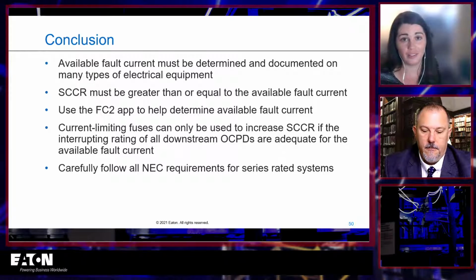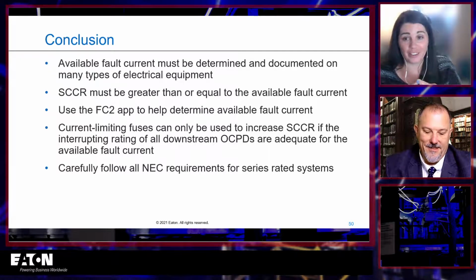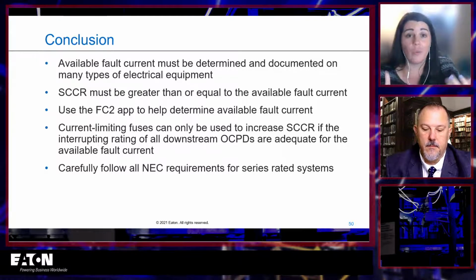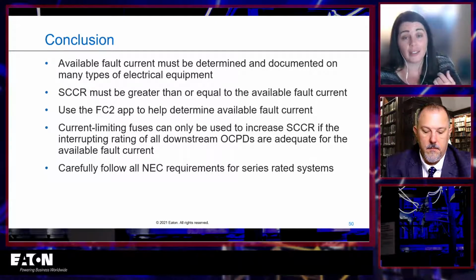So in conclusion, available fault current. We got to know what it is, right? We have to determine what it is. We have to document it. We have to actually field mark a lot of pieces of equipment, but at a minimum, document it. The SCCR, right, which is the rating for my whole assembly of equipment, that has to be greater than or equal to the available fault current.